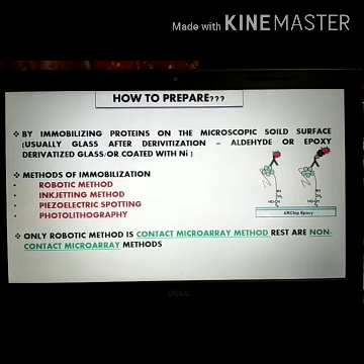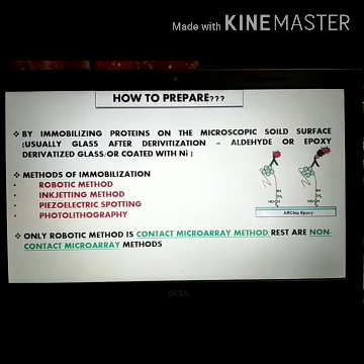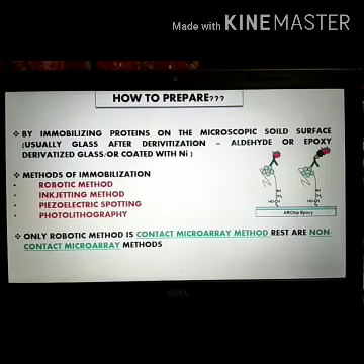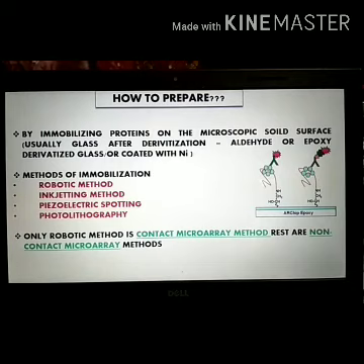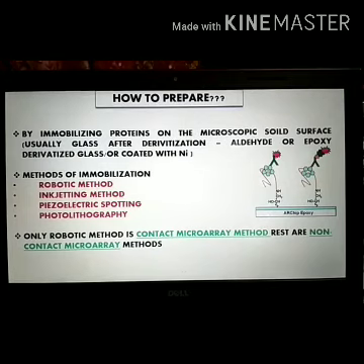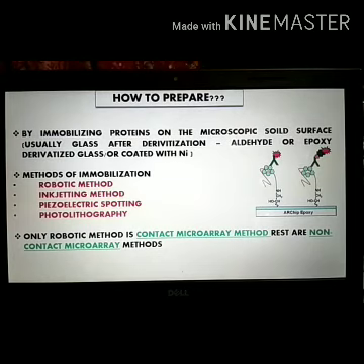The needle is generally filled with highly purified proteins, and then with the help of machines, it comes in contact with the substrate and loads the material directly on it. But in the non-contact microarray method, like the ink jetting method, the material is filled into a miniature hole known as the jet. Current is passed through the substrate, which also contains piezoelectric material. When current is passed through this hole, the liquid — which is our material — falls onto the substrate. So there is no direct contact between the arrayer or loader with the substrate.